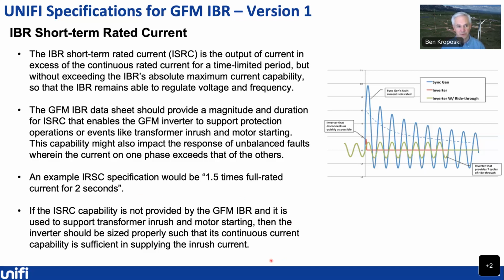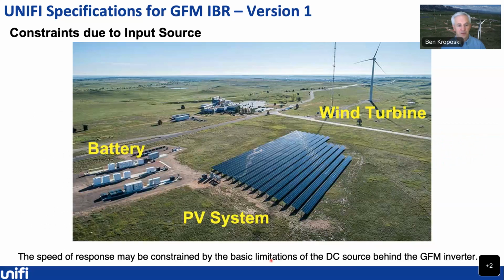The other constraint that you may have with grid forming technologies is what's on the DC side or the input source. So it could be things like a wind turbine, you could have a PV system, you could have a battery. Each of these is going to have sort of different response characteristics on the DC side of these inverters that may give you a difference in how they are performing overall in the context of the system.